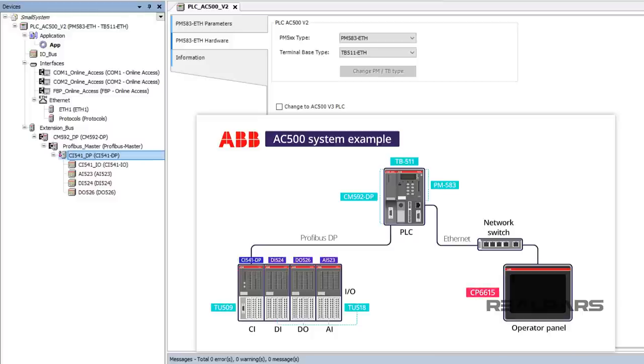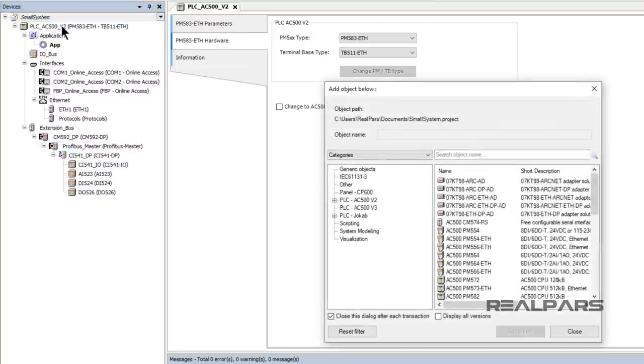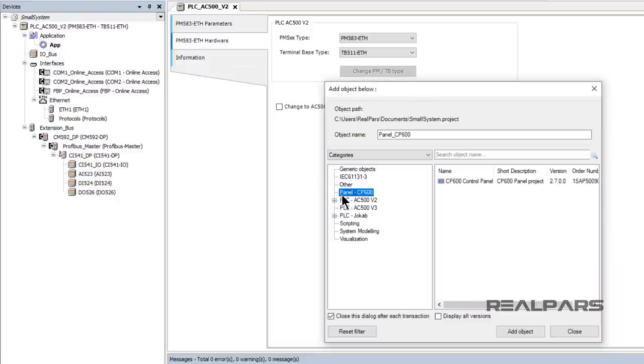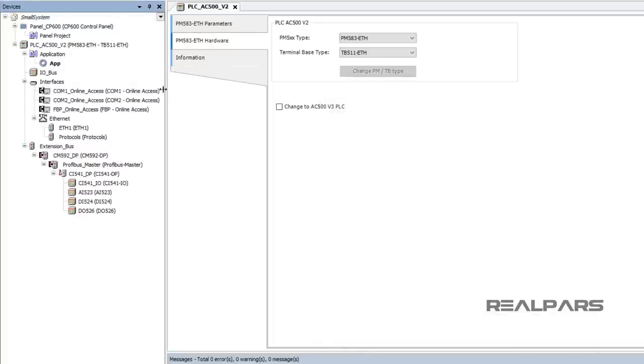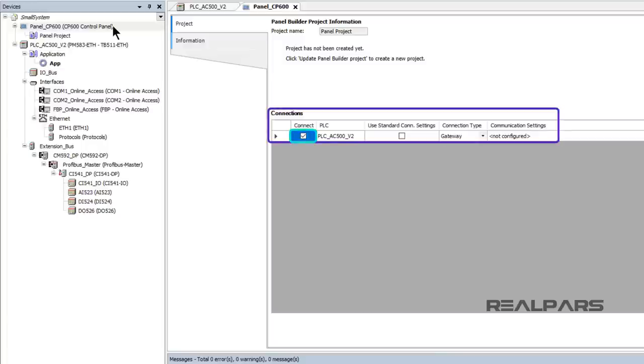Now I need to add the HMI panel to the hardware configuration. I right-click on the project name Small System and select Add Object. In the Add Object window, I select Panel CP600 in the left pane to filter the Device List and then select CP600 Control Panel from the list. I double-click on Panel CP600 in the Device Tree and when the Information Window appears, I see the connection from the CP600 to the CPU is selected by default.